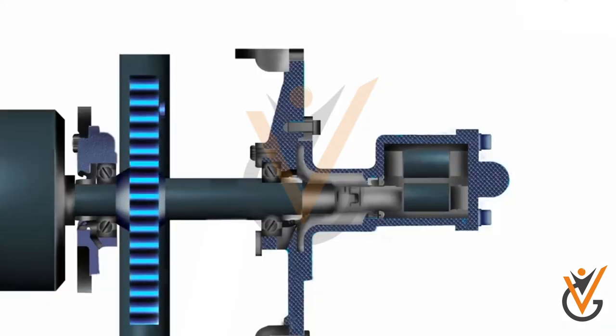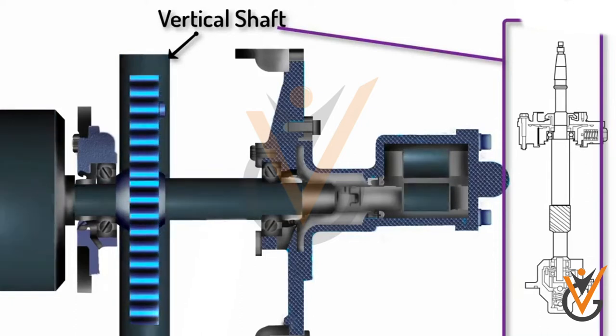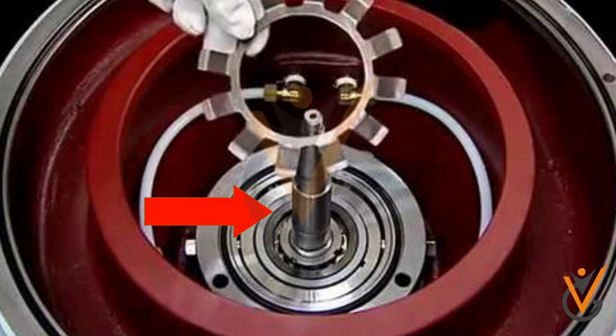Vertical shaft: The vertical shaft is used to transform the electrical motor output into rotational motion for rotating the bowl at high speed through a worm gear and horizontal shaft or belt. The material used for vertical shaft construction is an alloy of steel.